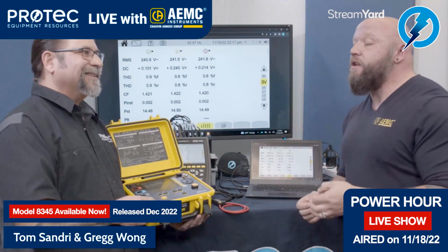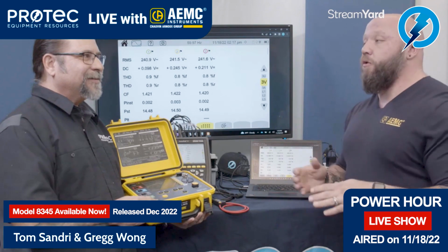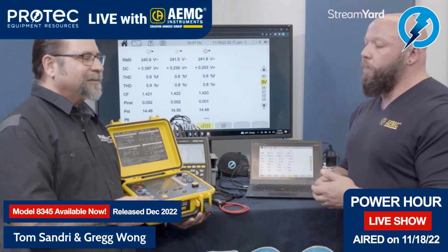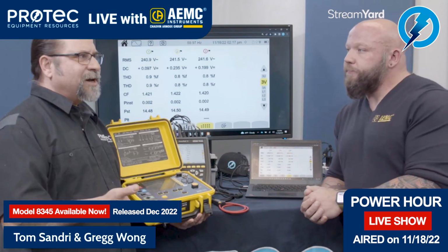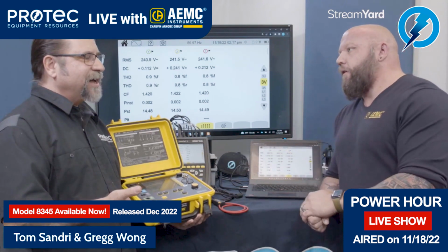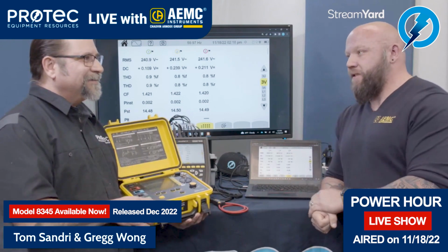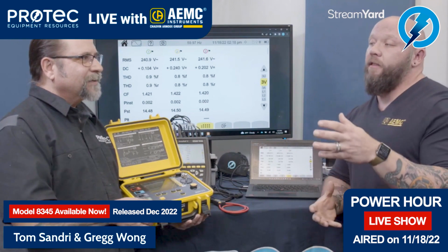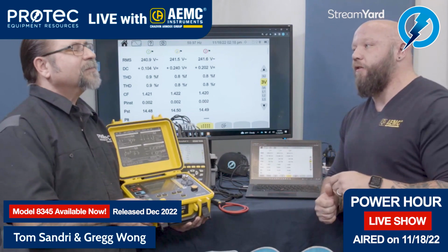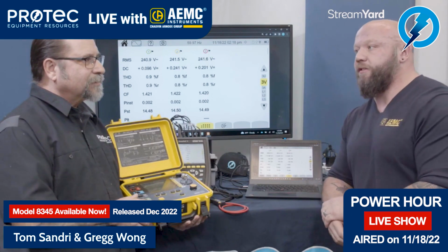I can get the individual footing resistance of that tower, both individual legs on a lattice tower or tripole, or just a monopole, which is obviously the newest style of towers. The cost savings of not sending that truck and everything out has virtually bought you your unit. It's a massive savings. It's an incredibly accurate method. We can verify the bond of the static overhead as well, how well that's working for us, and the influence of the other towers down the line.